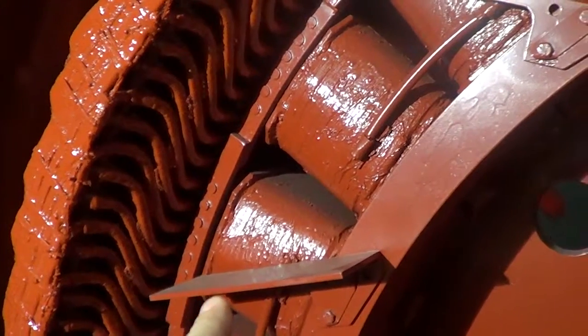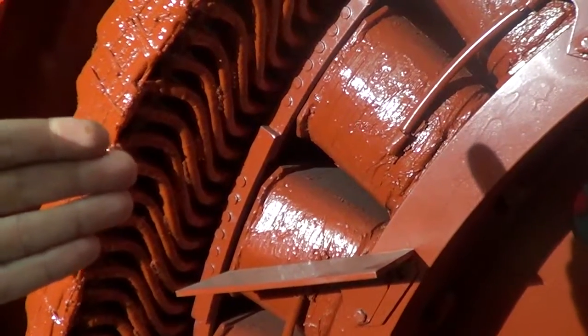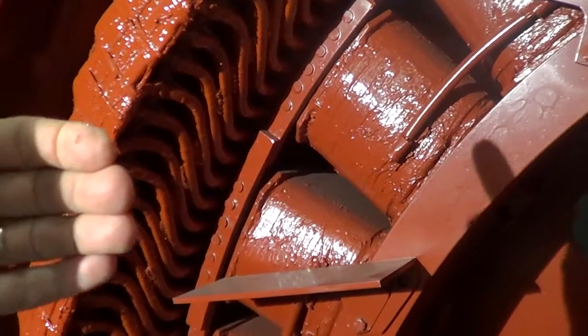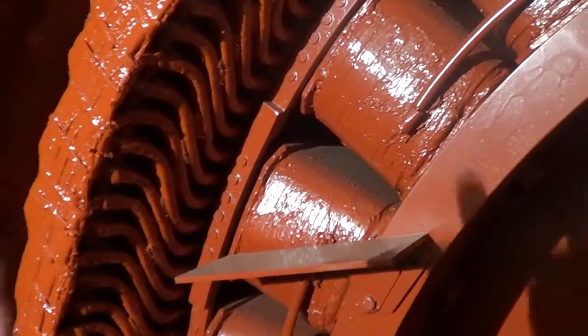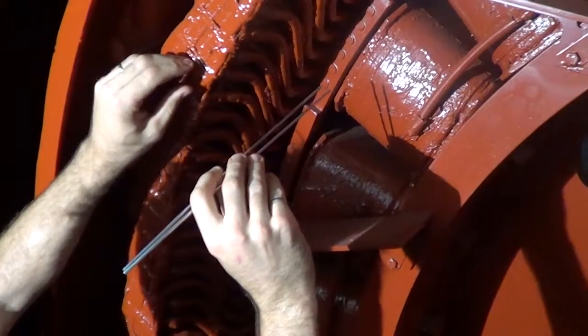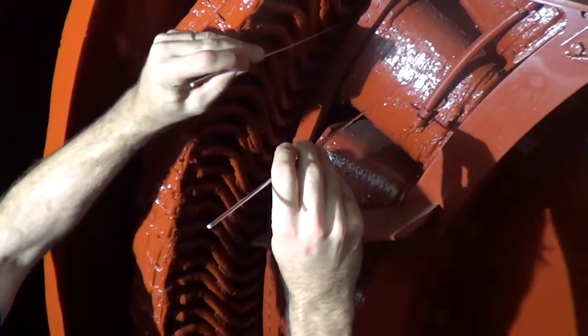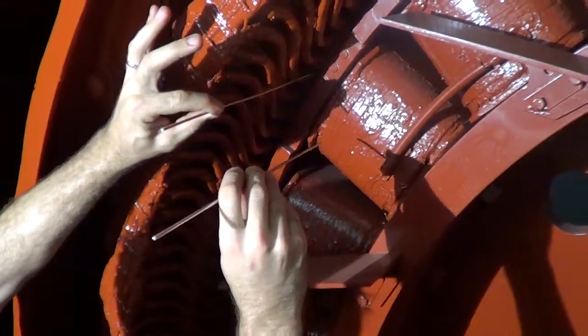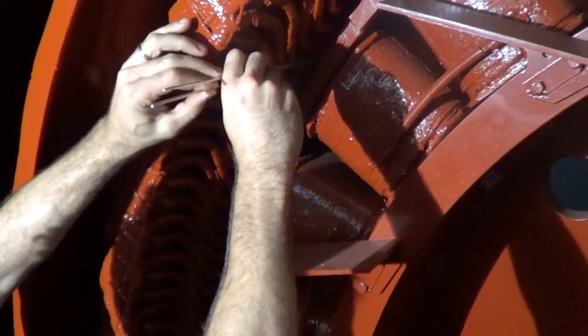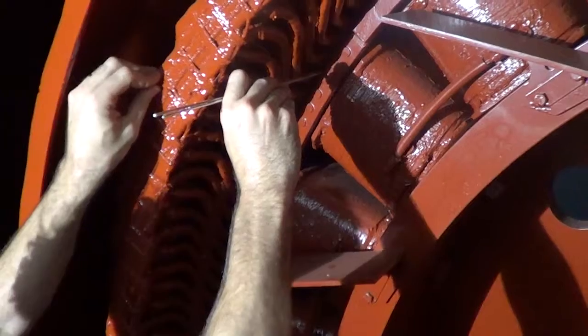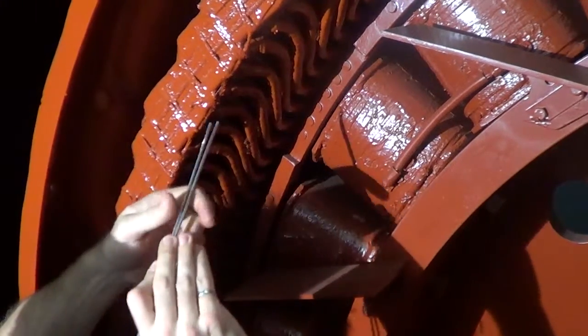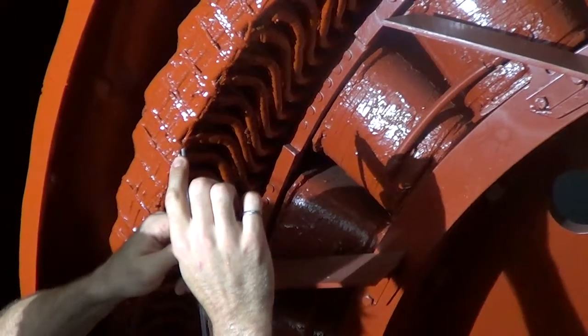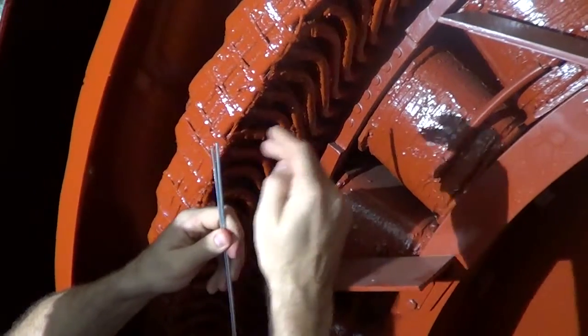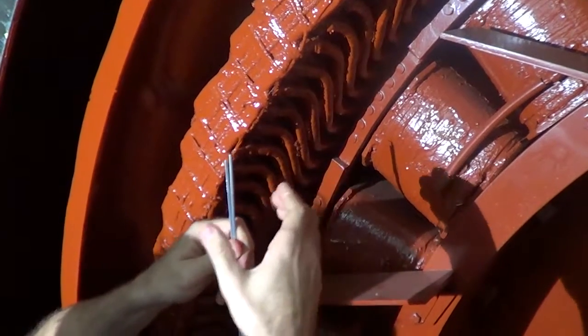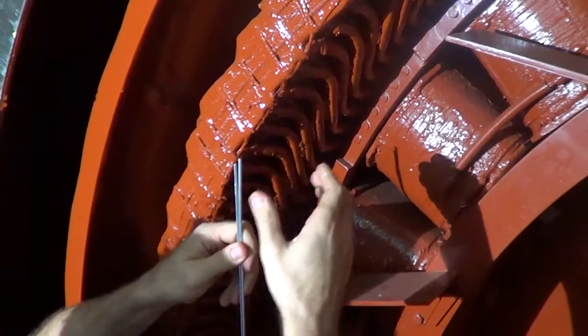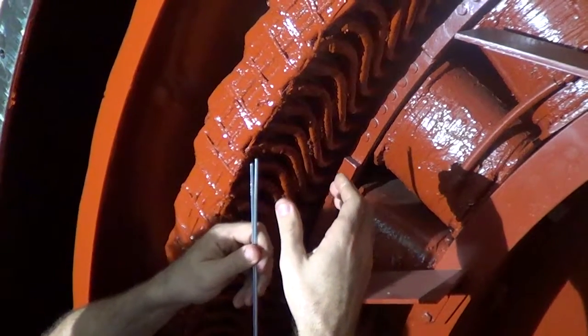Here we see the individual rotor poles installed in the stator core. Magnetic center is the ideal position where the rotor is perfectly centered axially within the stator core. To measure magnetic center, insert a TIG welding rod and touch the outermost lamination of the stator. Insert a second TIG welding rod and touch the outermost lamination of the corresponding rotor position. Pinch the rods together and remove. This will give you the relative distance of the rotor pole with respect to the stator iron. Duplicate this measurement on the other side of the machine, and that will determine any movements you need to make to achieve the best axial position. This is magnetic center for a synchronous motor.